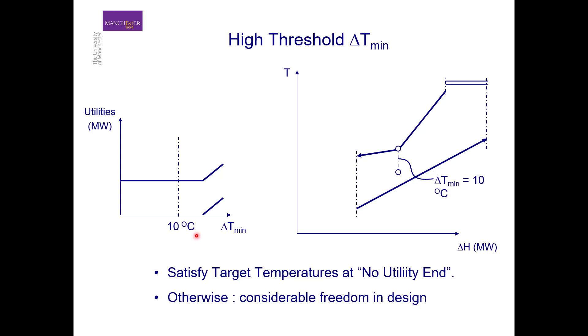The most difficult part of the design is the end of the process at the no-utility side. The cold utility is not present, meaning all the hot streams must be satisfied by the cold streams, because we don't have the option of rejecting heat from these streams to a cold utility. In contrast, on the other side of the process we have the hot utility, so some of the heat to the cold streams can be provided from the hot utility. The strategy is to satisfy temperatures at the no-hot-utility end first, then move toward higher temperatures where there is greater freedom in design due to the availability of the hot utility.